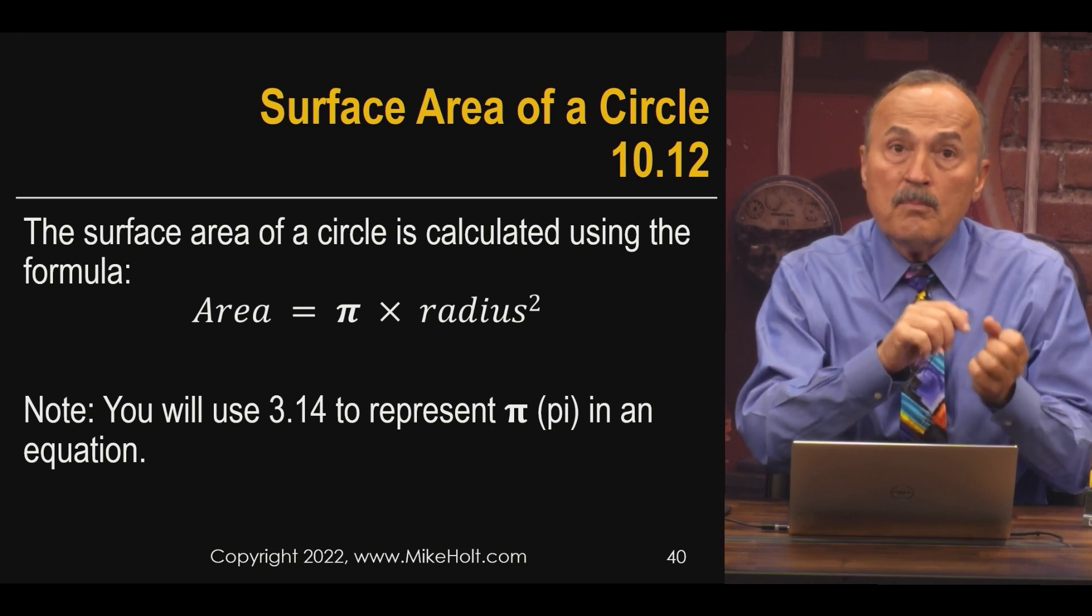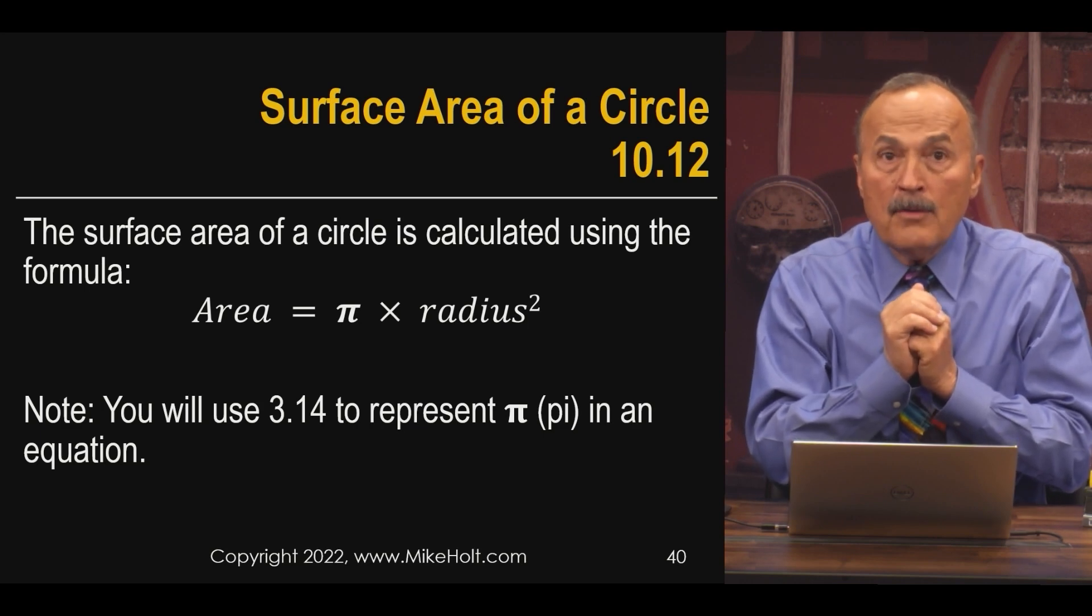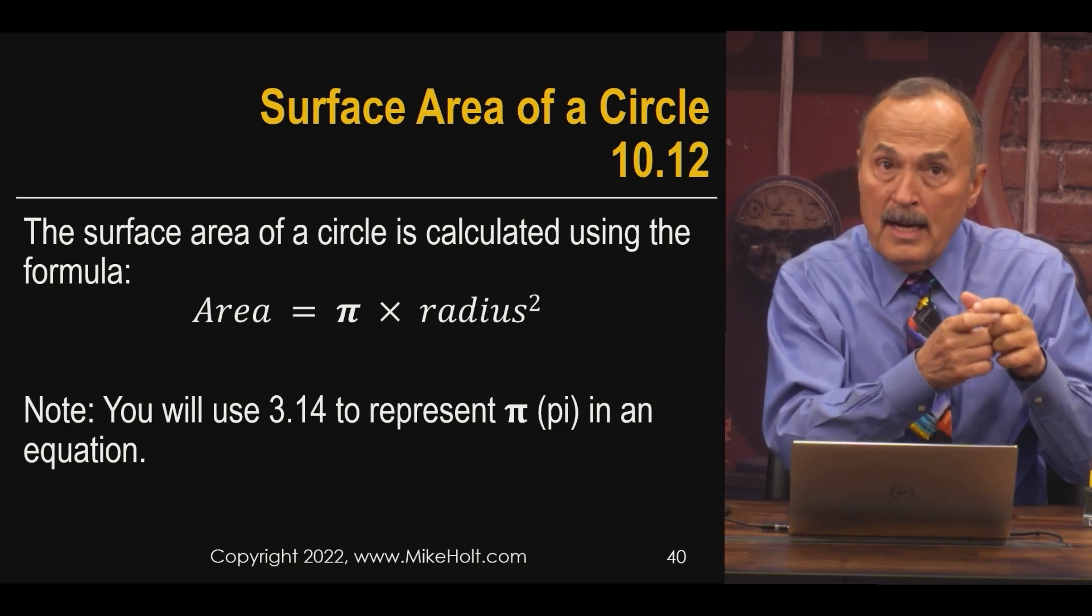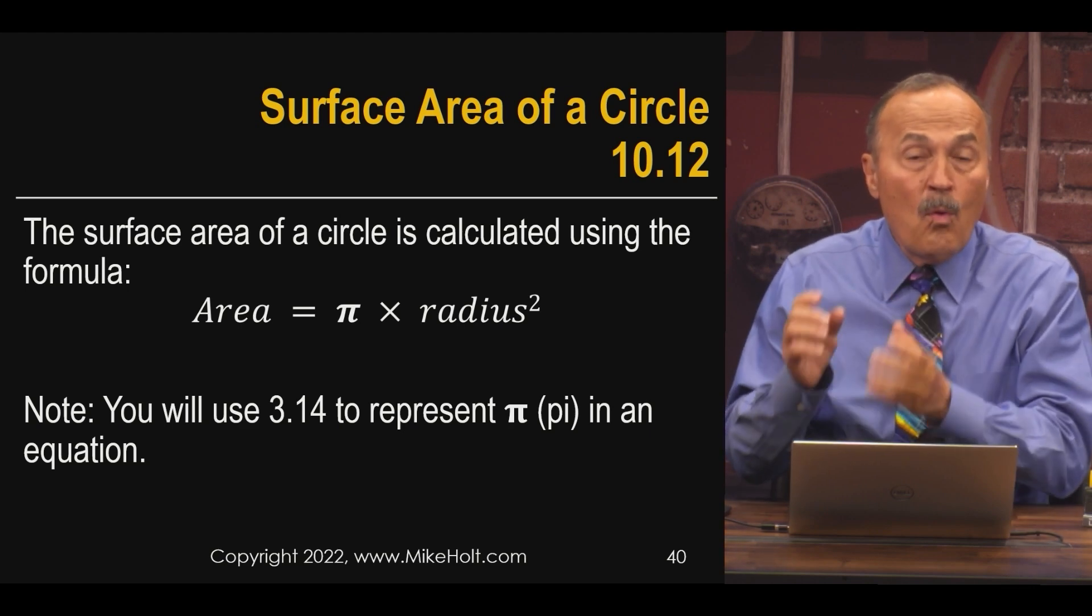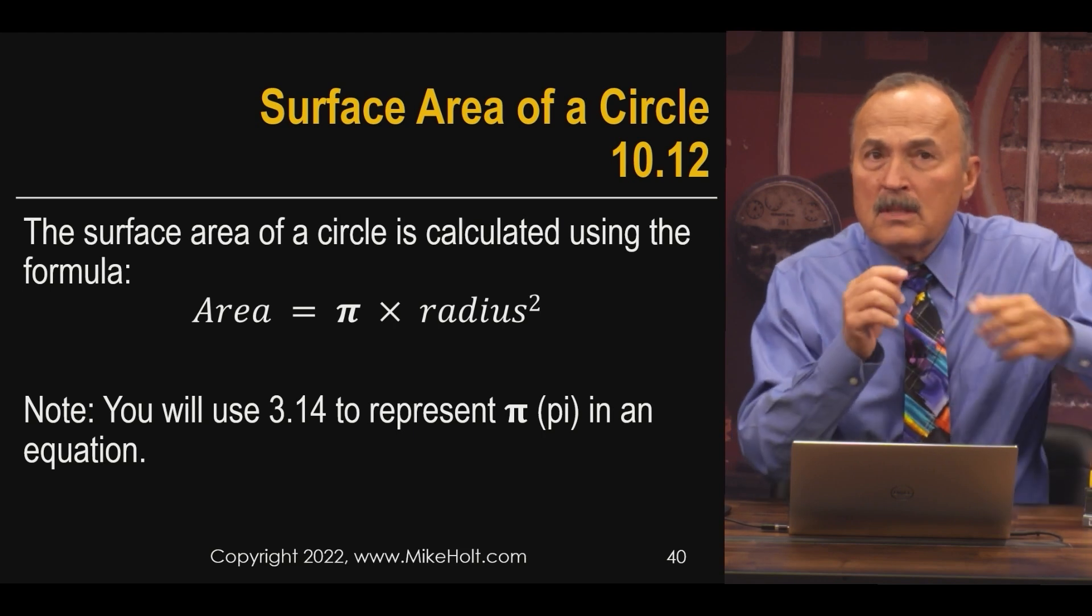The code tells you you can only fill it up to a certain percentage fill. The code book will actually give you the area of a circle for the pipe and the area of the wires, so you don't have to calculate the area of circles.